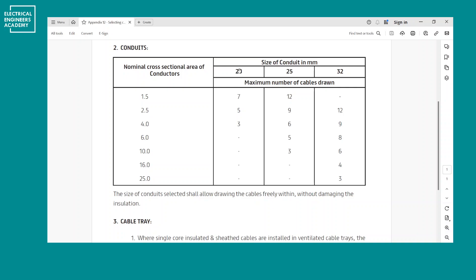To choose a conduit, as you can see here, the sizes are in millimeters: 20mm, 25mm, and 32mm. Please don't confuse this with millimeter square — this is the conduit diameter. When you say 20mm, that is the diameter of the conduit. When you say millimeter square, which is used for cables, that's the cross-sectional area. So the diameter will be different. When you say 16mm² or 25mm², that represents the cross-sectional area of the cable, which is pi r squared. For conduit, we specify the size as a diameter.